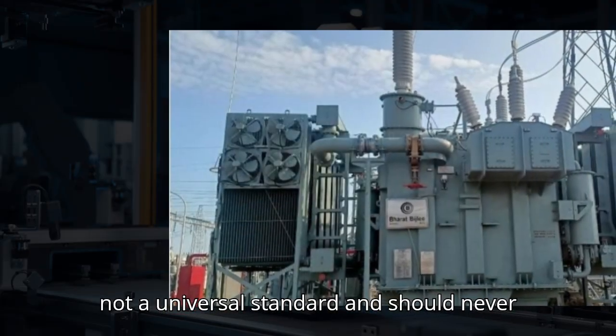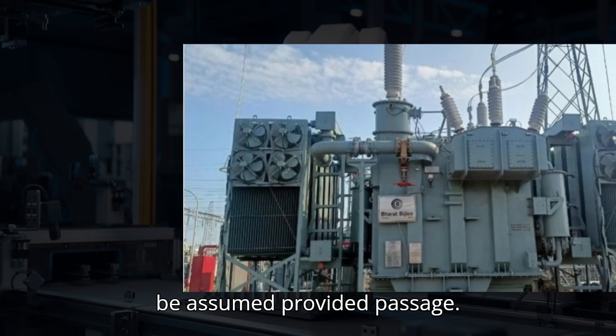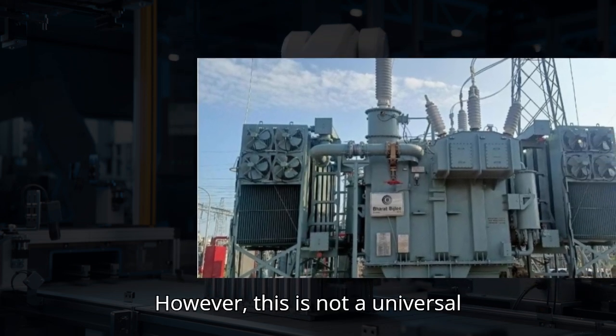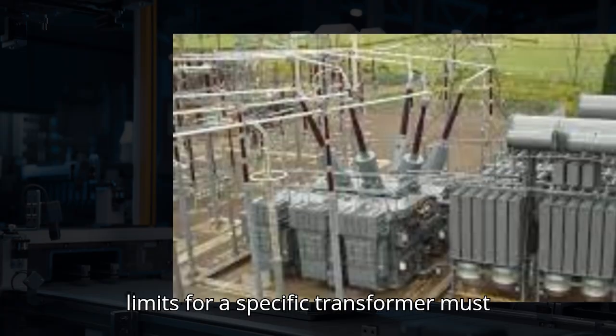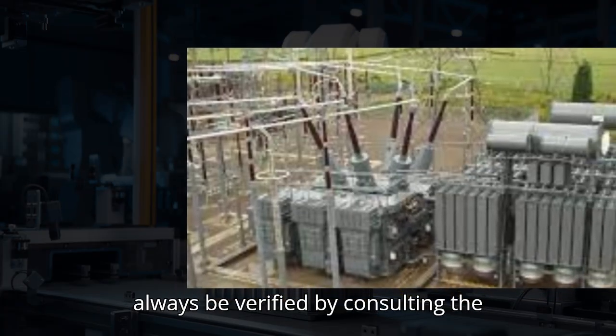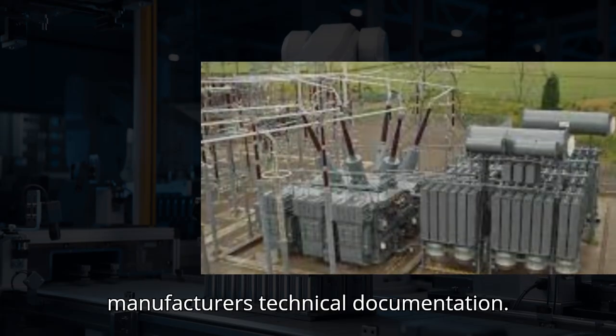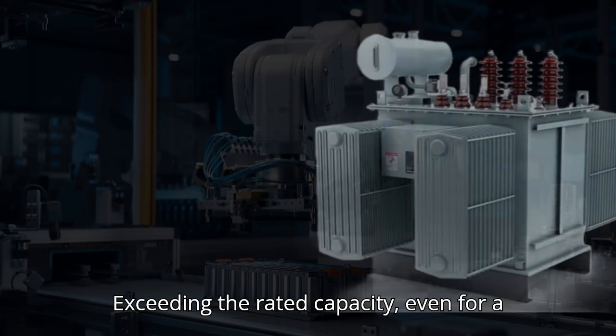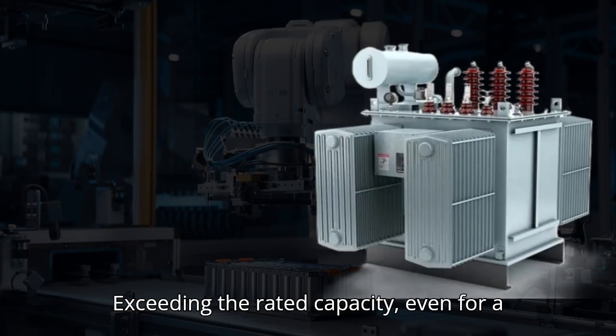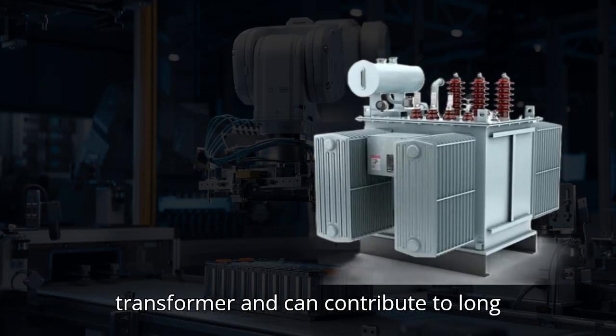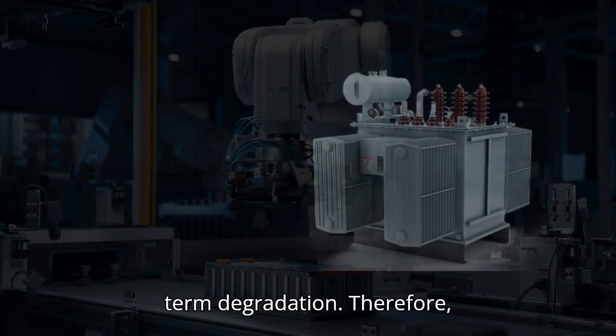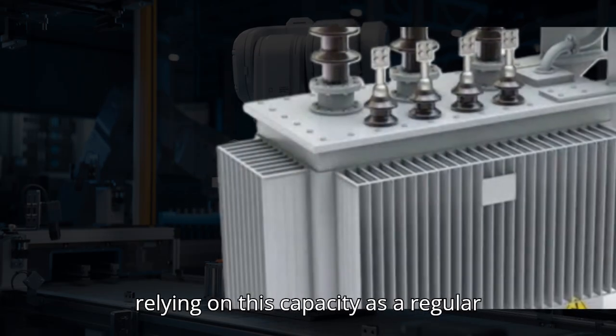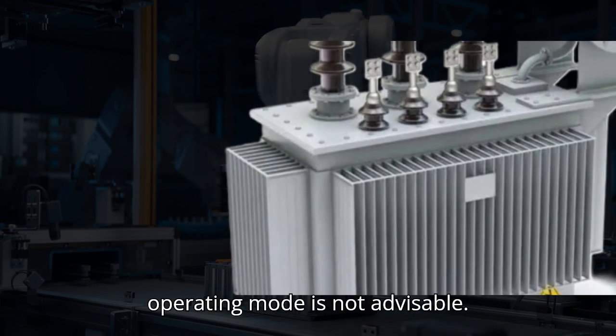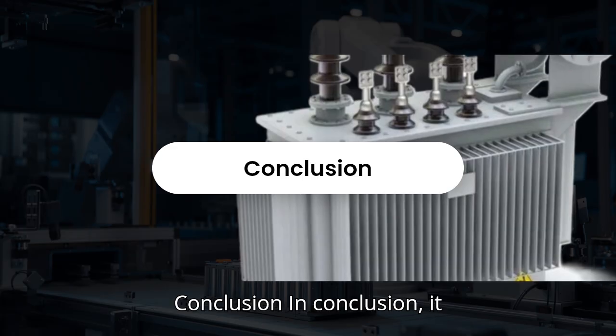However, it is crucial to recognize that this is not a universal standard and should never be assumed. The permissible overload limits for a specific transformer must always be verified by consulting the transformer's nameplate or the manufacturer's technical documentation. Exceeding the rated capacity, even for a short period, puts stress on the transformer and can contribute to long-term degradation. Therefore, relying on this capacity as a regular operating mode is not advisable.